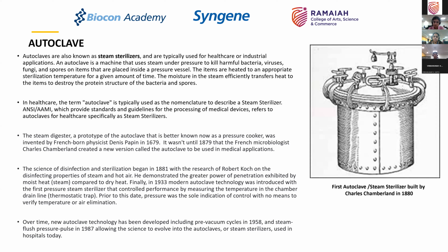If you look at the timelines, it took more than 50 years to arrive at the conditions which were critical for an autoclave to work. Over time, new autoclave technologies have been developed, including pre-vacuum cycles in 1958 and steam flush pressure pulse in 1987, allowing the science to evolve into autoclaves or steam sterilizers, which are used in hospitals and industry today.